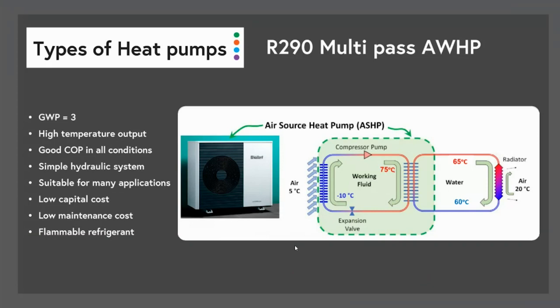The thing about multi-pass heat pumps is they're good in all conditions, and this hydraulic system is very simple. This heat pump we're talking about today is what's called a hydronic monoblock. What that means is that the refrigerant's all contained within the outside unit. No refrigerant leaves the unit. It's a fully sealed system. And so there are only hot and cold connections on it, which makes it a plumbing appliance. So it's a very suitable appliance to be sold into the plumbing channel, and it can therefore be a replacement for things like boilers.